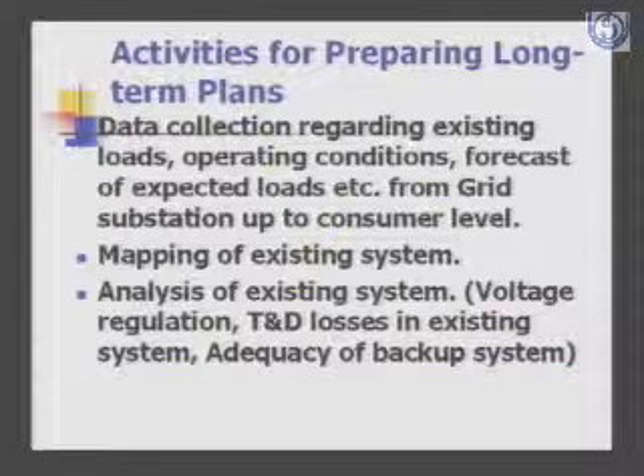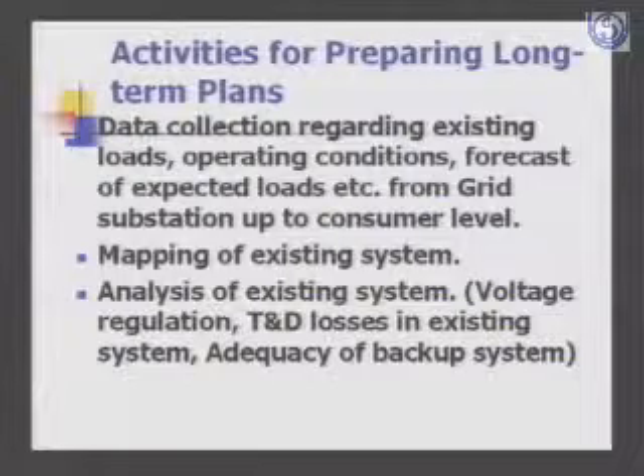So the first thing is attempting a mapping of the system, and that, let me tell you, is 90% of the job, because it takes a long time doing a field survey to get the data. Mapping of the system requires that you map each and every section of the line. In a transmission line of 100 kilometers, it may be Moose conductor running throughout. But in a distribution system, the sections involved will be different in size and length over that same 100 kilometers. Even the span length is not constant in a distribution system.